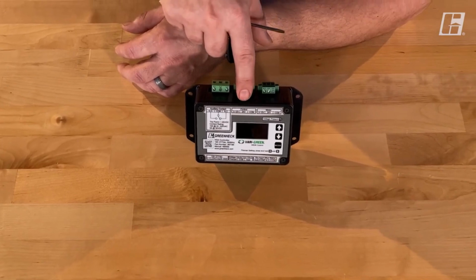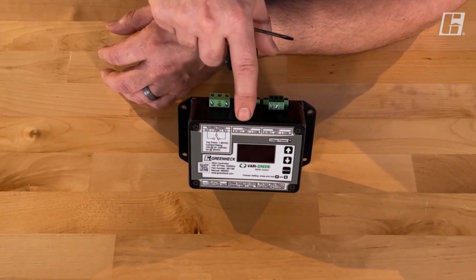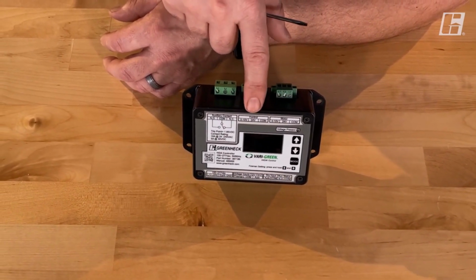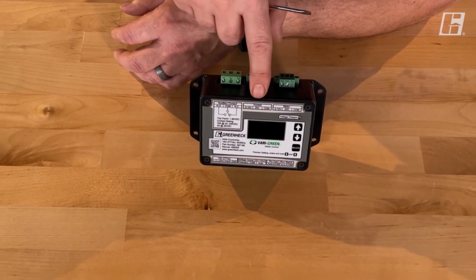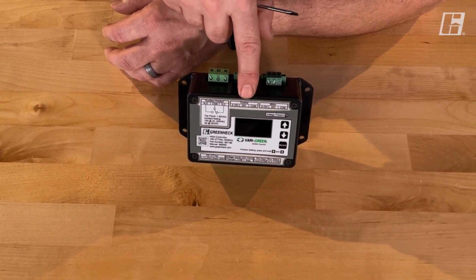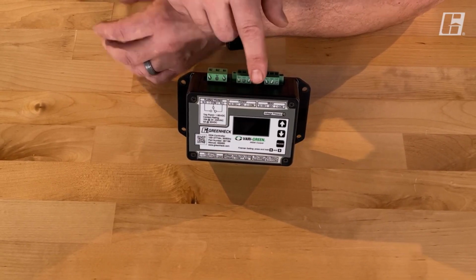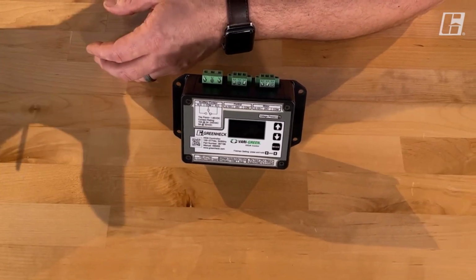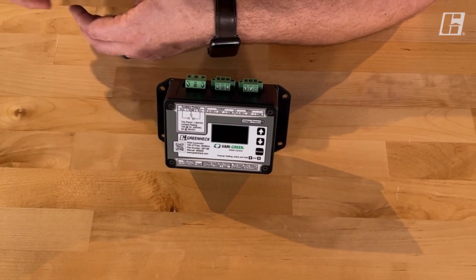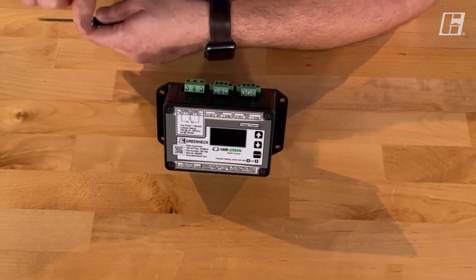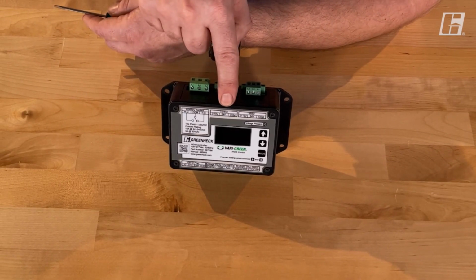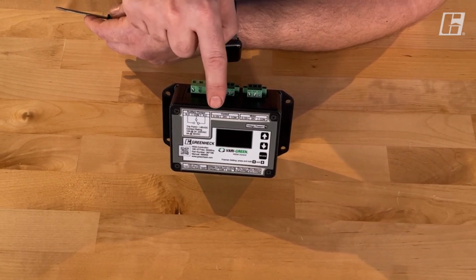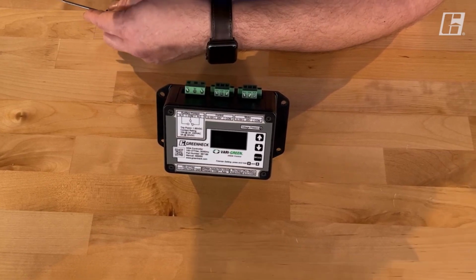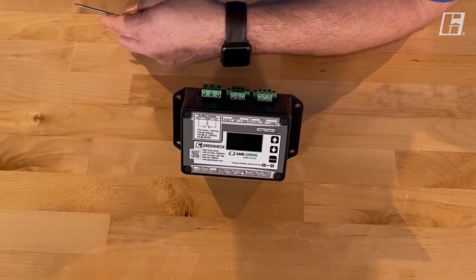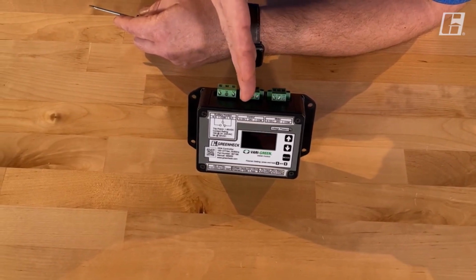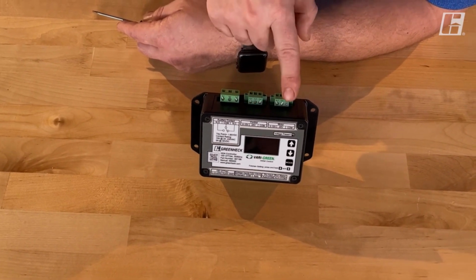Our next terminal set is labeled control. Now this again has common, 24, and 0 to 10. This 24 terminal is 24 volts DC output, and it's meant to power other controls, like a Vari-Green constant pressure controller or a Vari-Green remote dial. That's what that 24 volts is for. Common, and then the 0 to 10 volt is an input. We're taking other controls' speed reference, bringing it into the HOA, and when appropriate, it then passes it out to the motor.